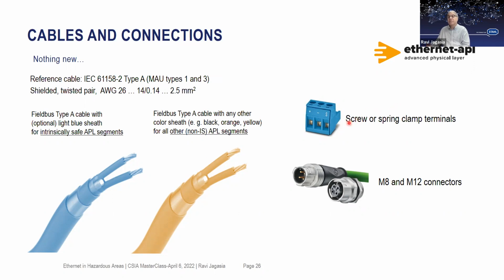Standard terminals, screw or spring clamp, or the M8, M12 connectors. The typical M12 connectors will be used in the div 2, zone 2, and the screw terminals will be used for the zone 1, div 1 termination. It is intrinsically safe. As you can see, a blue terminal, so there is absolutely no problem that you can unscrew a cable or unplug a connector and still be safe in a hazardous area.